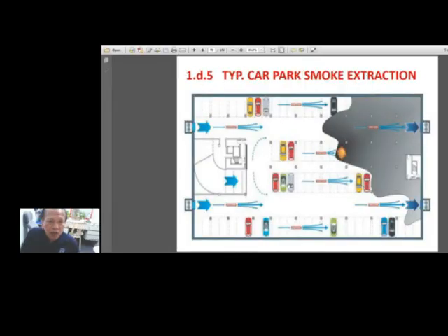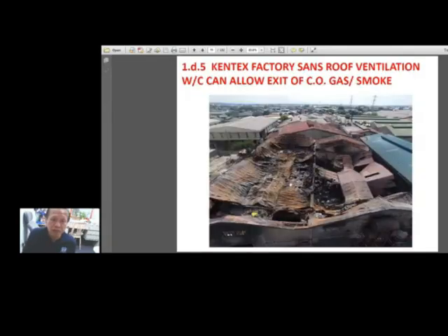Okay, so parking areas should also be provided with carbon monoxide detector with exhaust fan. Here are 2 exhaust fans on this side, and there are also 2 exhaust fans on the other side. These 2 here on the left side will be blowing fresh air inside, and this will be bringing out the air inside the parking area. That is when you have cars parked that are running and there's not enough oxygen or air inside, so you produce carbon monoxide.